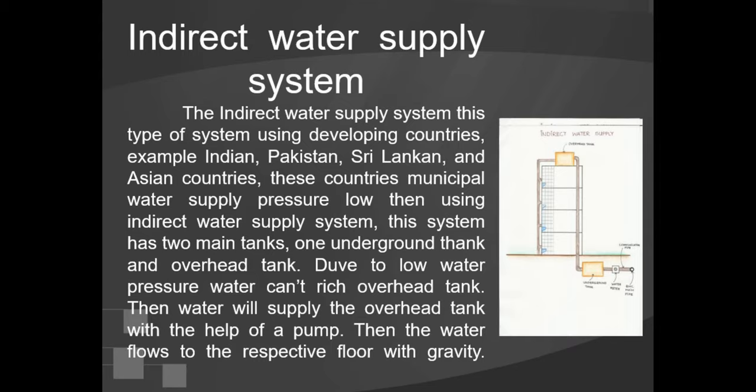Examples of countries using indirect water supply include India, Pakistan, Sri Lanka, and other Asian countries. When municipal water supply pressure is low, the indirect water supply system is used. This system has two main tanks: one underground tank and one overhead tank. Due to low water pressure, water cannot reach the overhead tank directly, so water is supplied to the overhead tank with the help of a pump. Then water flows to the respective floors by gravity.